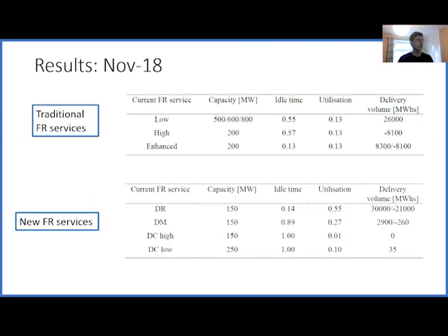This is just comparing the traditional frequency response services in 2018 with the new frequency response services. There's quite a lot here, and I don't have much time, so I'll just pick out one thing: dynamic moderation's idle time is 90%, meaning 90% of the time it's not being used, so the frequency is within plus or minus 0.1 hertz.